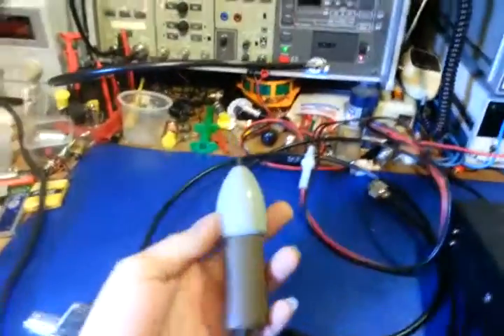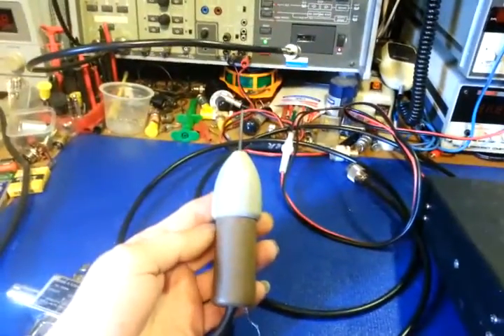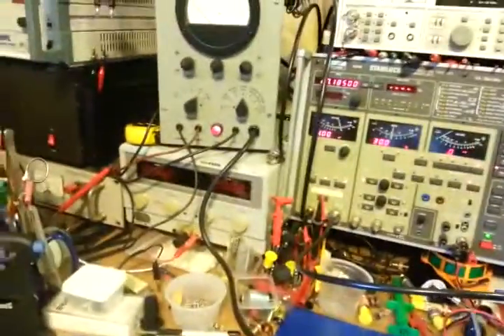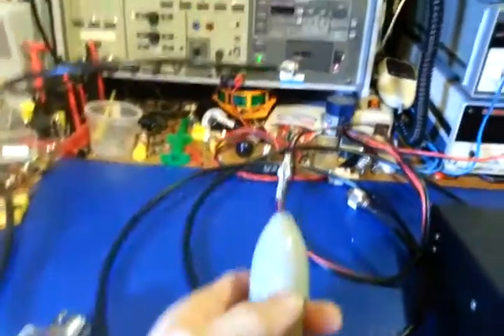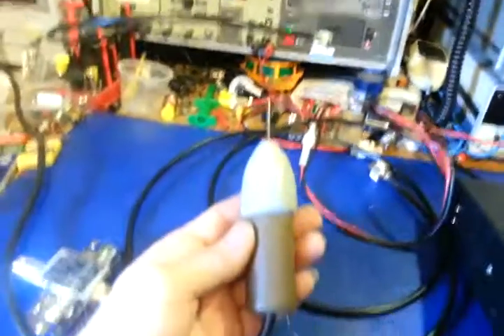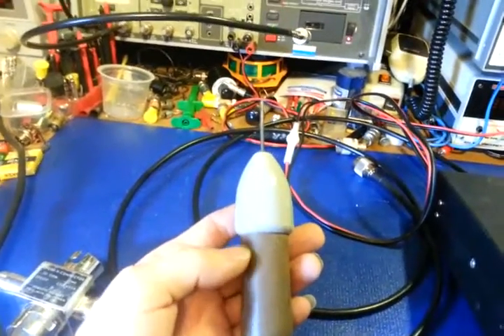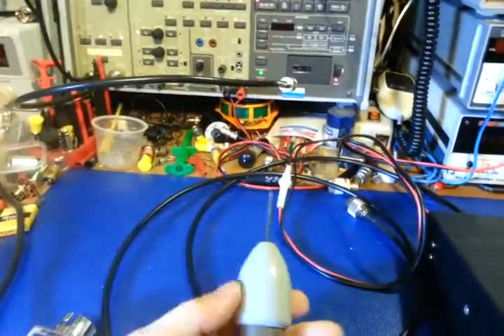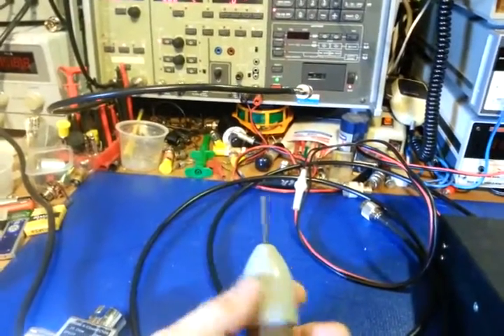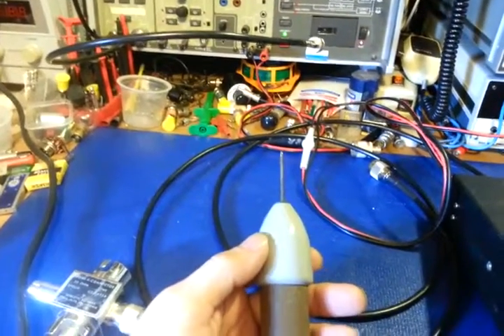And one of the things that made that possible was this rather unique AC probe that comes with it, and it's permanently attached to a double shielded coax cable. But this probe actually has a very small vacuum tube built inside. And the meter's been on for a while. You see the red light there at the bottom, and it's actually warm. And that's one of the reasons this meter can read frequencies so high.